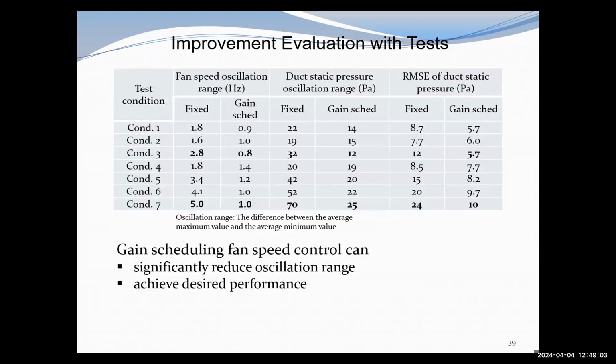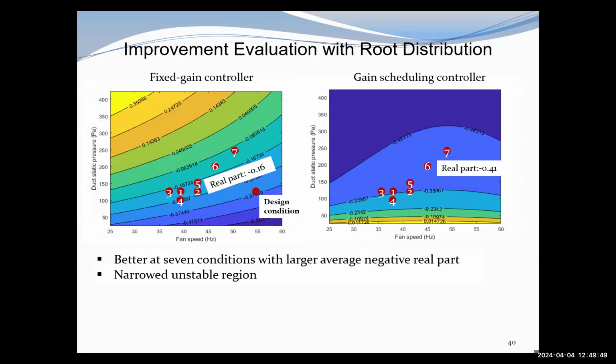And to quantify it, we calculated the fan speed oscillation range and also the duct static pressure oscillation range. This is the difference between the average maximum value and the average minimum value. We can see that under the worst condition, condition 7, the fan speed oscillation range can be dramatically reduced from 5 to 1 Hz. So we can see that the gain scheduling fan speed control can significantly reduce the oscillation range and achieve the desired performance on the dynamic operation conditions. And that's for the tested conditions.